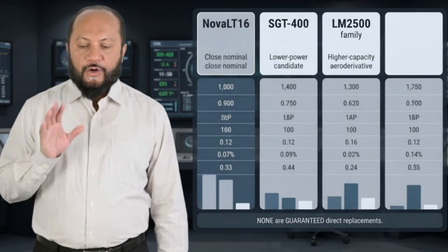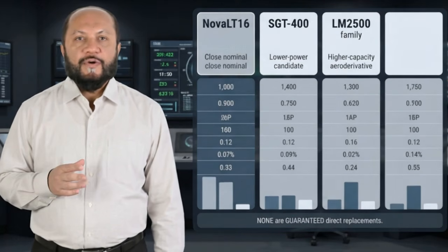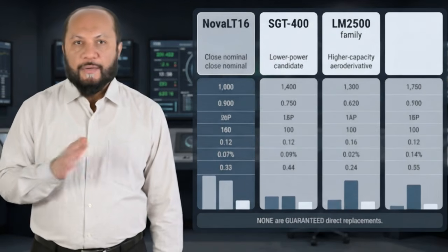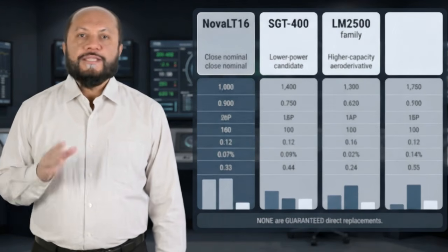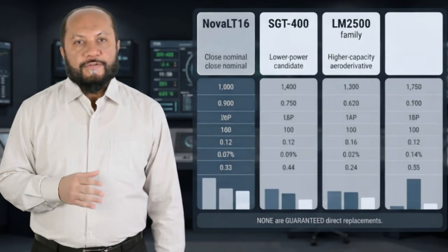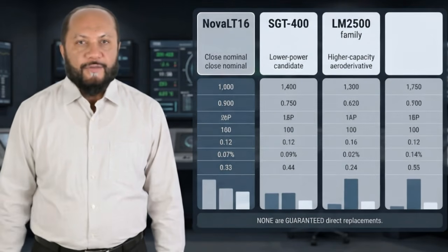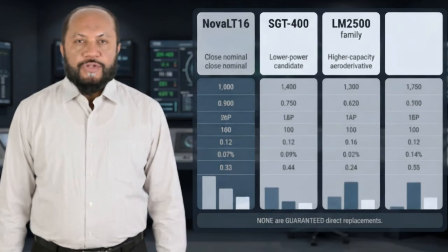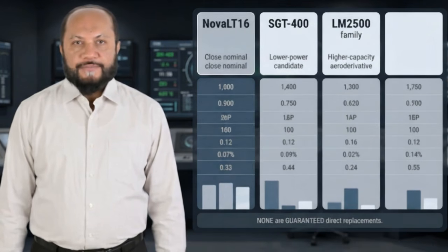So the final comparison should be framed carefully. Nova LT16 is a close nominal power class candidate. SGT400 is a lower power candidate. LM2500 family equipment is a higher capacity aeroderivative candidate. None should be treated as a guaranteed direct replacement. The most important takeaway is that the complete integrated system matters: turbine, compressor, package, controls, fuel, auxiliaries, emissions, maintenance, and plant objectives. A replacement study must prove the match across the full operating envelope.